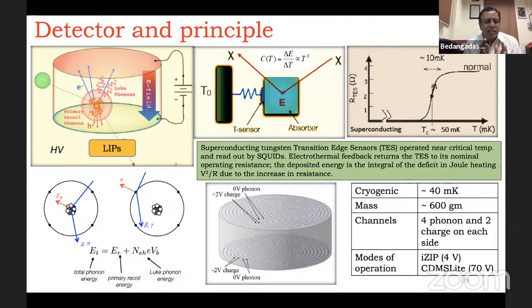So what one measures in this detector is the total phonon energy coming from the primary recoil energy as well as from these Luke phonons, which depends on the number of electron-hole pairs created times the voltage, of course, the charge and the voltage applied to the detector. Now, these signals are taken through superconducting tungsten transition edge sensors. These are operated at the critical temperature of this material, and that is around 40 to 50 millikelvin. That is where it is kept.